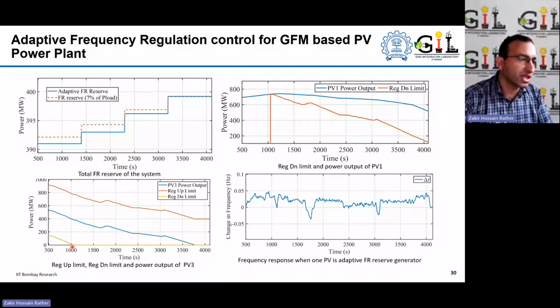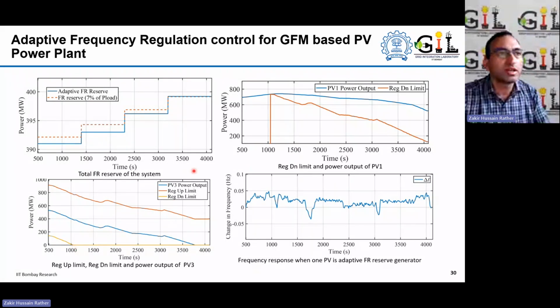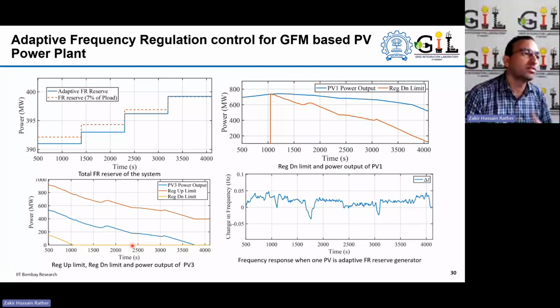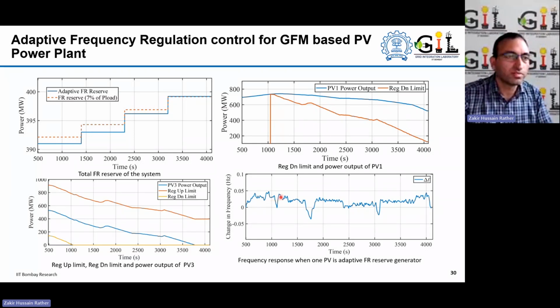What is happening around this time, since the power plant output is decreasing, on the upper side, the up reserve side, it is maintaining that 7% load equivalent reserve. But on the downside, post this, there is a decrease in the reserve because of the falling output of power plant 3. So then automatically, post this point where we are falling short of the reserve on the lower side, power plant 1 starts contributing to it. So power plant 1 starts decreasing its power output to maintain this down reserve as well, equal to the up reserve in the system. And this is the frequency of the system in this case.